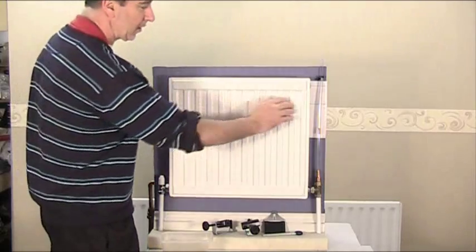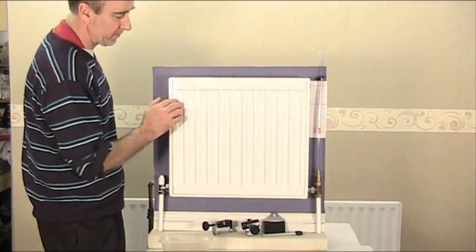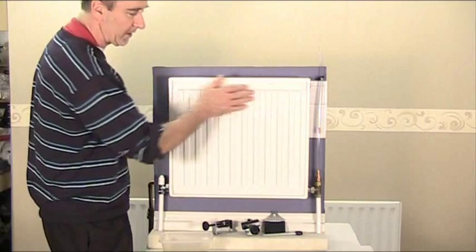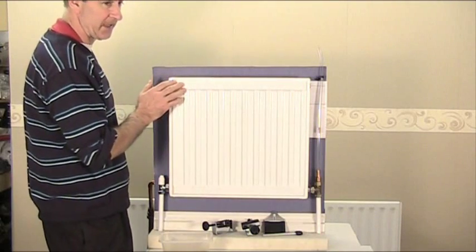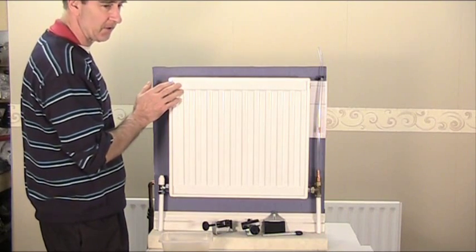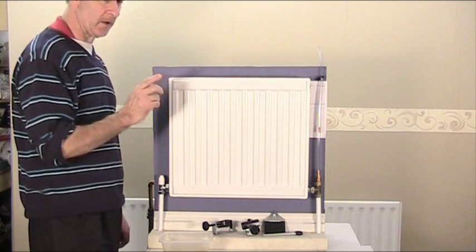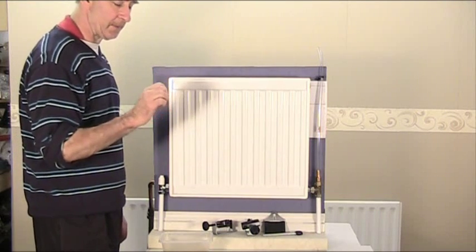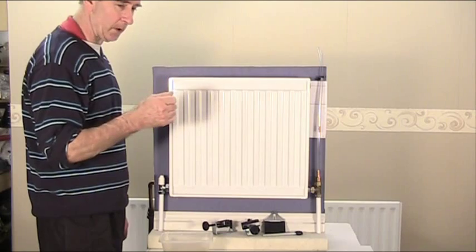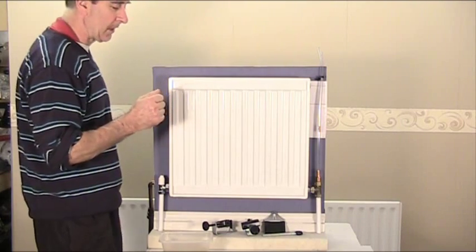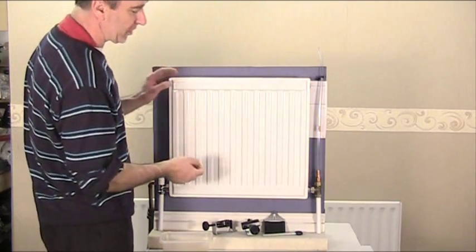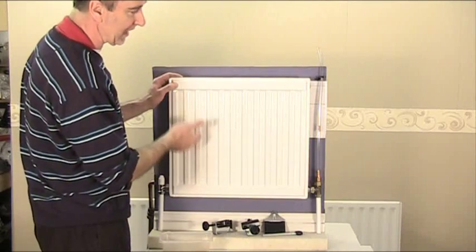Now if you are getting cold pockets or cold spots above the top of your radiator, it is 99% going to be air trapped, so you need to release that. But bear in mind on the pressurized system, you need to maintain the pressure manually underneath the boiler as you're doing it. Anyway, this is just a quick demonstration to show you what is actually happening in the radiator.